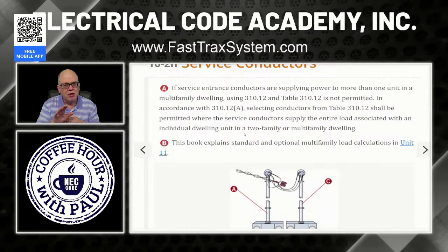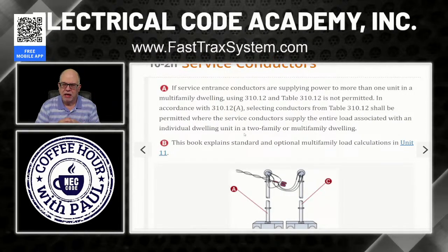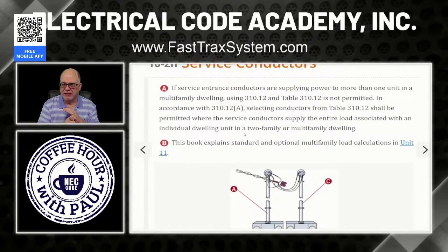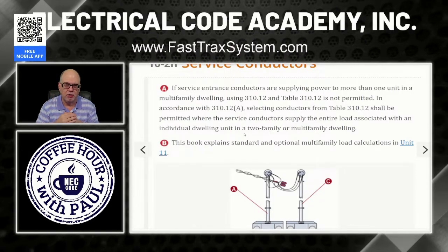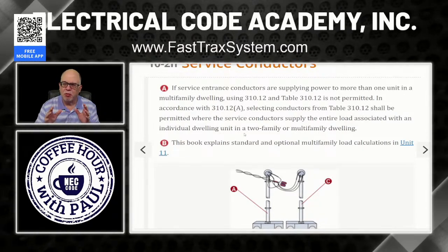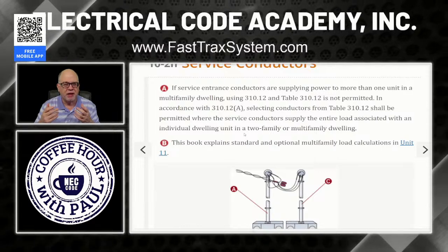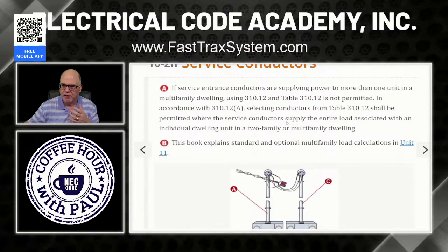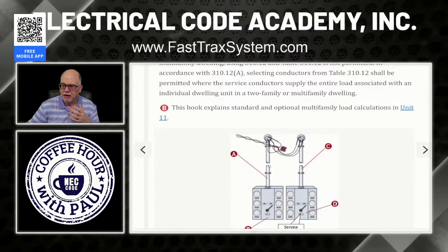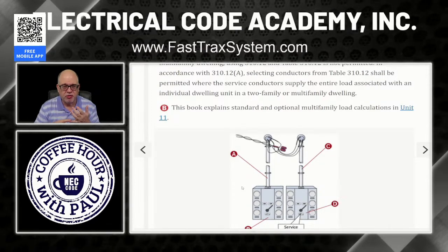Now, if you're not familiar with Table 310.12, that is the 83% rule that you hear so many people talk about. I encourage you to pause and go watch that, because it's going to be done in a separate video where I explain the nuances of 310.12. But in this video, I just want you to know that you can't use that. The reason we get that out of the way up front is because these service conductors aren't supplying the entire load of the building, right? If you look at this illustration, these conductors are supplying only these loads. They're not supplying the whole building, so they don't have the luxury of using the 83% rule, okay?